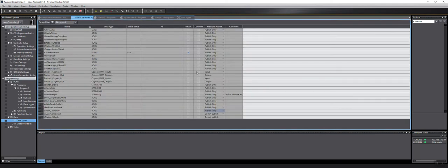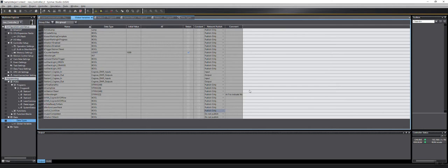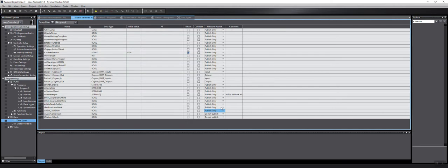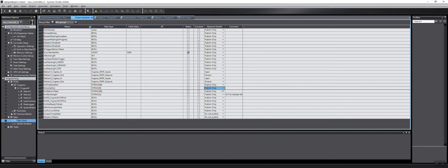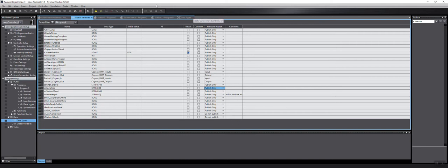So it's important to note that only global variables can be exported into an HMI development. And furthermore, the only variables that can communicate to the PLC are those that are selected as publish. If you have do not publish, the HMI will not be able to see them or redirect to those variables. So please make sure you have the proper variables established as publish.